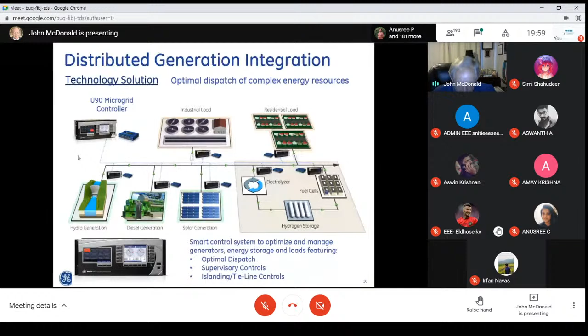So we took a microprocessor-based relay in the upper left here, a U90 microgrid, and we added logic to that relay to become the microgrid controller. Its objective was to make sure the load was satisfied continuously, minimize the use of the diesel, and maximize the use of the other resources. These blue boxes are all high-speed communications devices, so we were looking at data on a continuous basis. This has been very successful. This is called Bella Coola Village, a rural village in British Columbia.